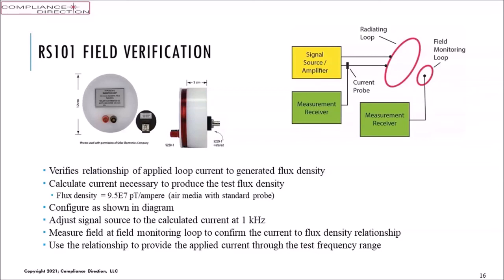All right, next up, what is the general formal requirement for calibration of the test equipment? Do we have to use the services of an external accredited ISO 17025? Well, that depends on your accreditation. If you want an accredited body to endorse you, you're going to have traceable calibrations, traceable to NIST or ISO 10012. And they call out several things like SAE ARP958 for antenna methods and various and sundry things. But bottom line is it needs to come back, in the U.S., to NIST traceable, National Institute of Standards and Technology, and or the ISO 10012 for the international approvals. So you need to somehow get to that level of calibrations.